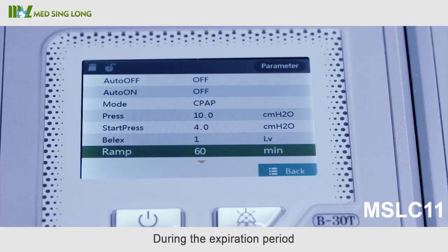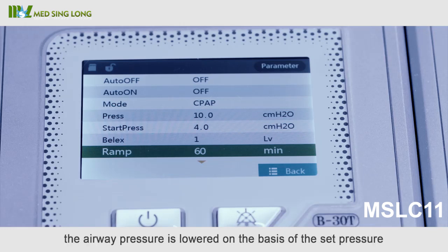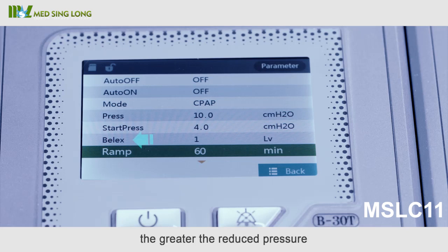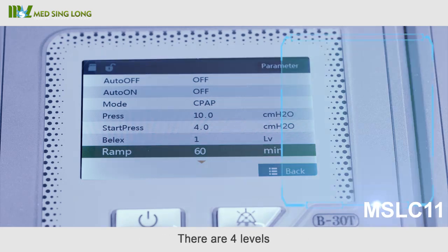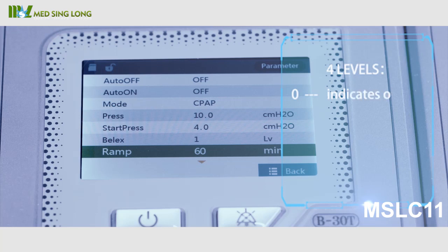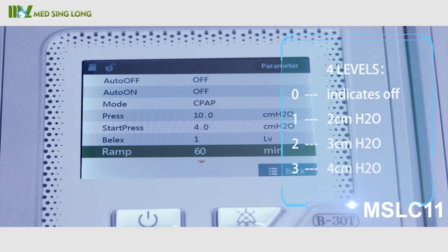Belex: During the expiration period, the airway pressure is lowered on the basis of the set pressure, and the larger the level, the greater the reduced pressure. There are four levels: level one equals two centimeters of water pressure; level two equals three centimeters water pressure; and level three equals four centimeters water pressure.